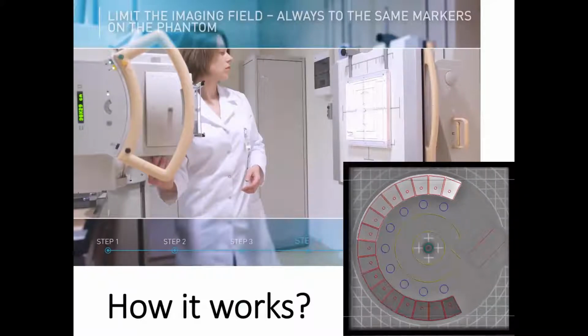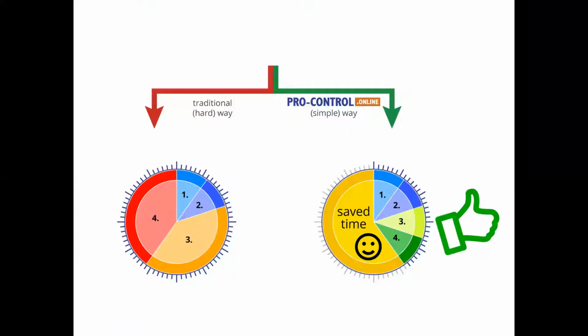Basically, everything comes down to a patient substitution method. So instead of taking an X-ray of a patient, you X-ray a phantom. As a result, you get an image of what is inside the phantom. Then on this image, you have to look for different features, analyze this image to get to know what the device is showing. So, for example, if a mammography unit will miss a small tumor in the breast.